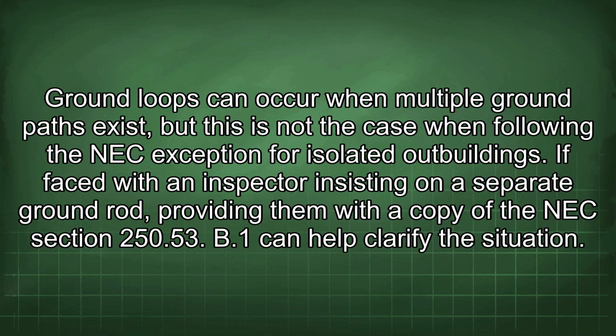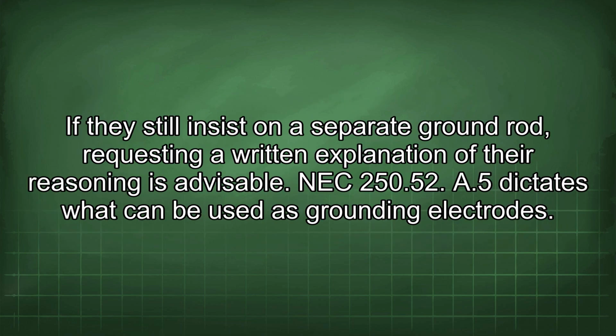Ground loops can occur when multiple ground paths exist, but this is not the case when following the NEC exception for isolated outbuildings. If faced with an inspector insisting on a separate ground rod, providing them with a copy of the NEC section 250.53(B)(1) can help clarify the situation. If they still insist on a separate ground rod, requesting a written explanation of their reasoning is advisable.